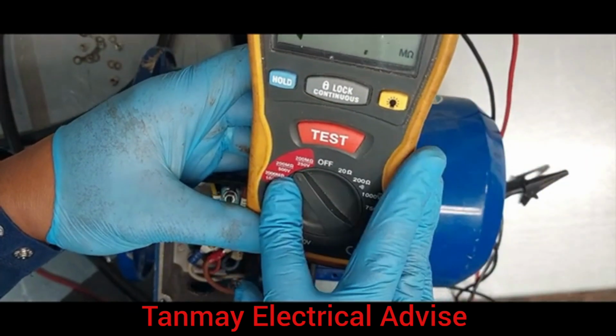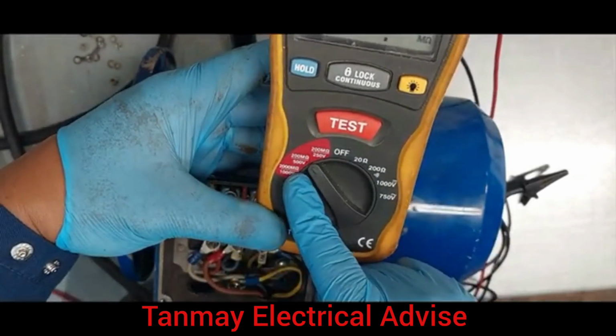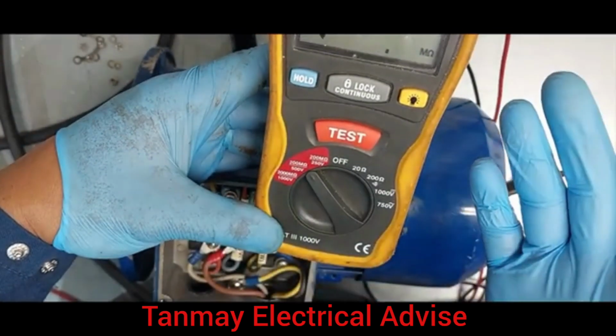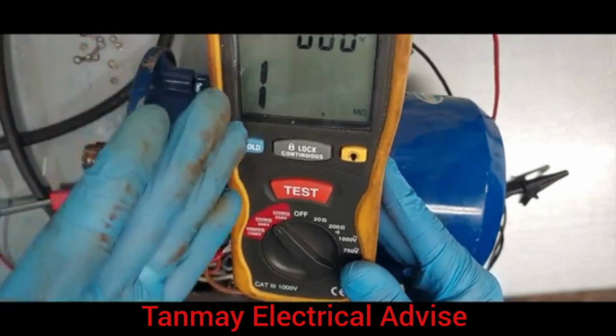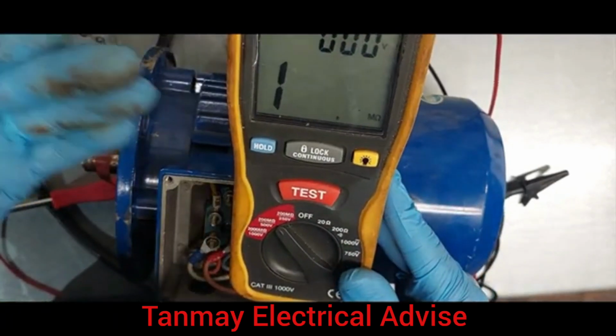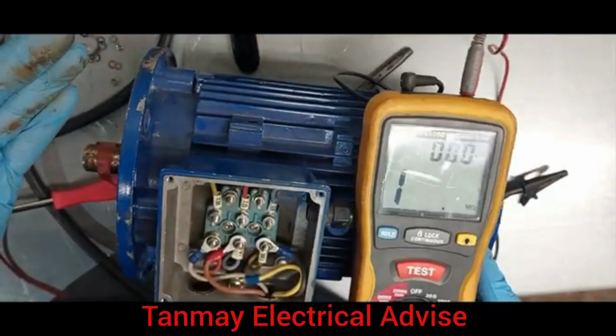Now we're going to inject 500 volt DC. This is a DC voltage. So we're going to inject 500 volts. Once we inject 500 volts, we expect to get returns of between 1 mega ohm and 2 mega ohm. Anything less than 1 mega ohm is a fail.